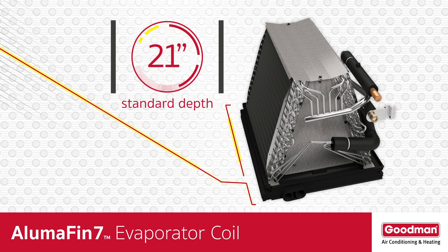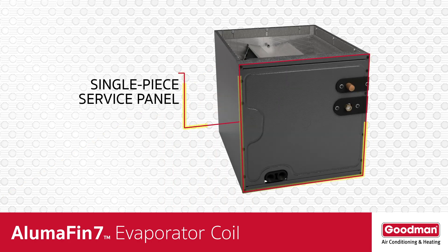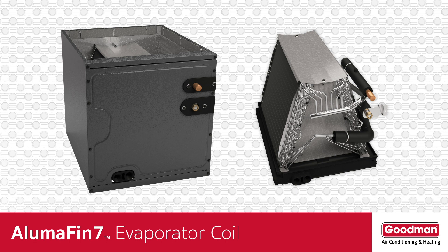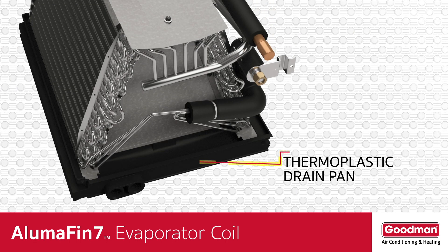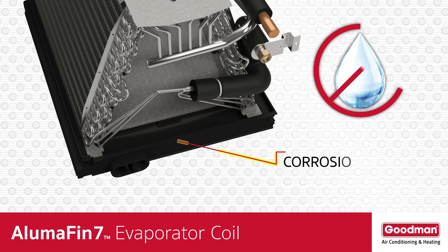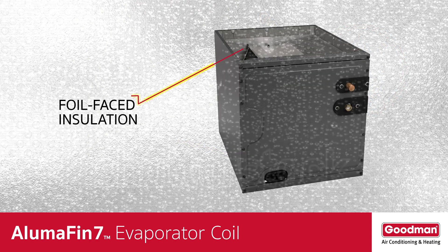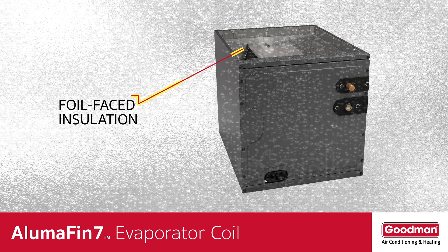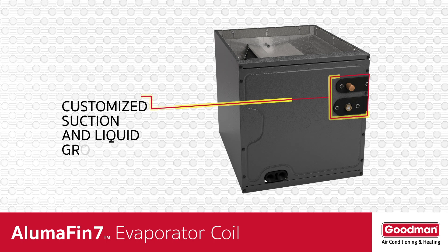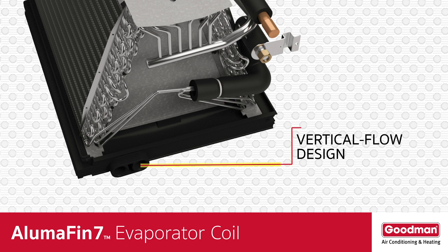Additional features include: 21-inch depth for easy access and tight installations; optimized for 410A refrigerant; single-piece access panel with tight seal to keep conditioned air from escaping; Flowrator mounts on the access panel for easier servicing; drain pan provides outstanding condensate management; thick drain pan rail to keep the drain pan secure; corrosion and mold resistant thermoplastic drain pan with no water retention design; foil-faced insulation covers the internal casing to reduce cabinet condensation; seal-tight customized suction and liquid grommets for easy installation and removal; and a thermoplastic drain pan with secondary drain connections featuring a vertical flow design allowing for upflow and downflow installations.